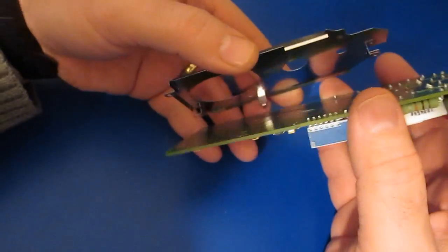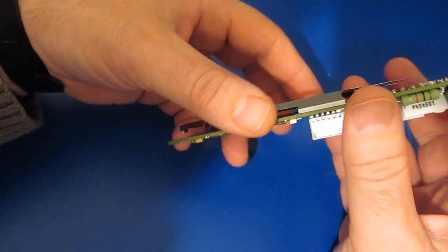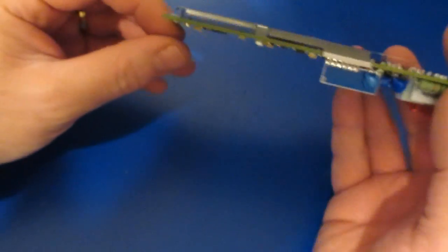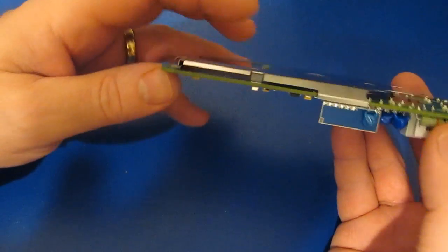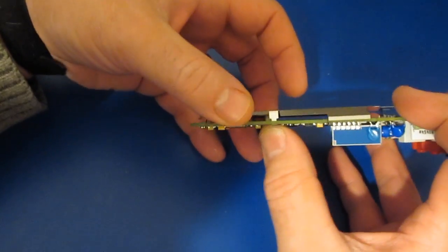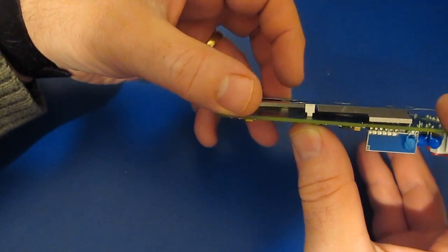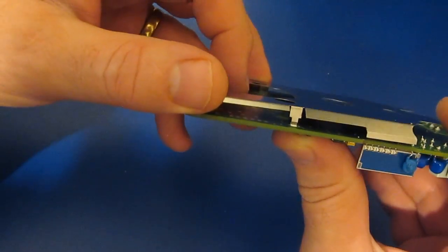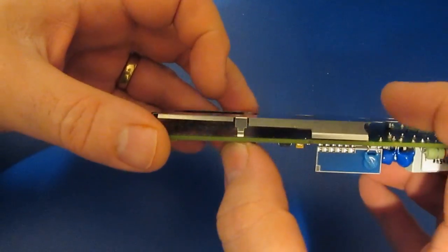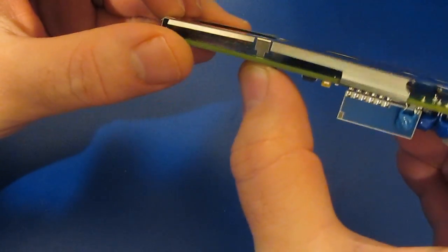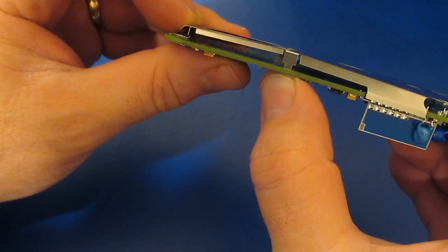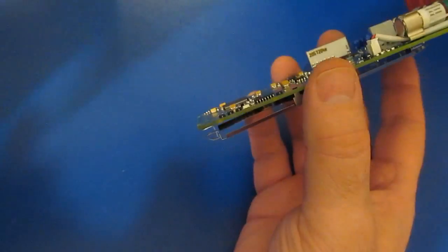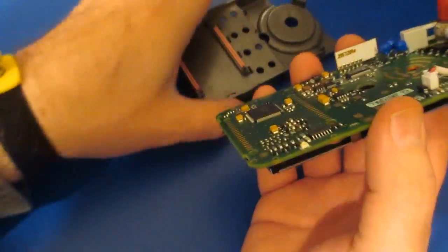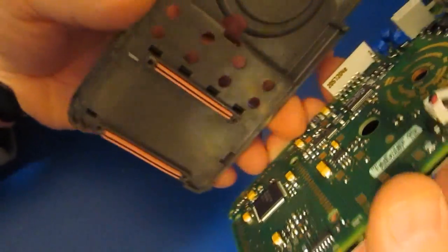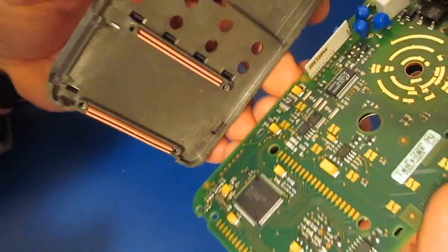When I first took this meter apart, I pointed out that the shield was bent. You can see it actually sits quite flat on the board, so there's no real problem with it. But if you look at the video, it looked like these tabs were not pushed down into the board, they were sitting up like this. Then the operator who assembled the meter tightened down the screws, so you ended up with something like this. I looked at the cover where these tabs fit through, and there don't appear to be any clearance issues with this.